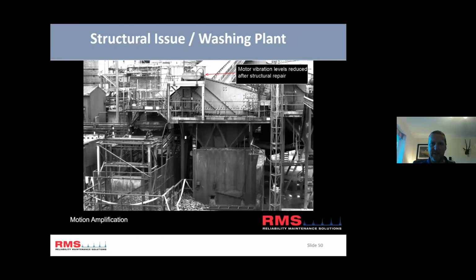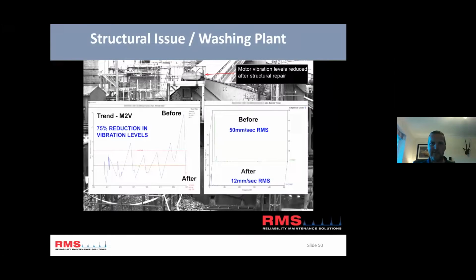This is the shot afterwards. You can see there's a lot less vibration, and it went from 50 down to 12 after they'd done that repair. I think they also did that on the run - I don't think they shut down for that. So that was pretty good; they didn't have to shut down the feed into the factory.